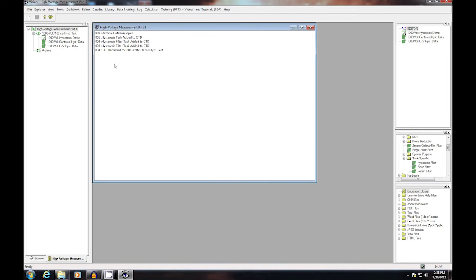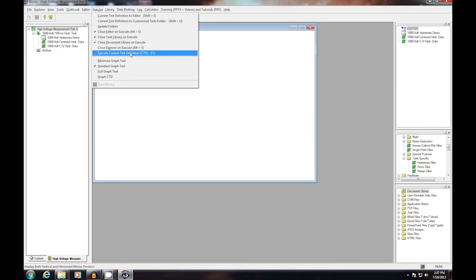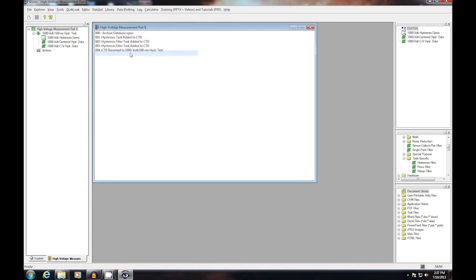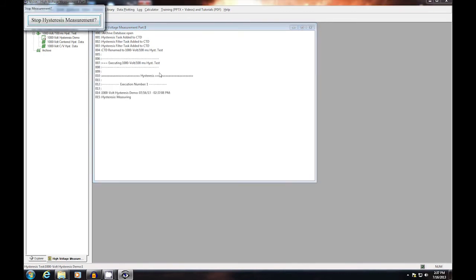The experiment is now ready to execute. I need to turn on the amplifier and set it to voltage out. Then I select data set, execute current test definition. As a measurement is being made, a stop button appears that allows you to stop the hysteresis measurement during execution.